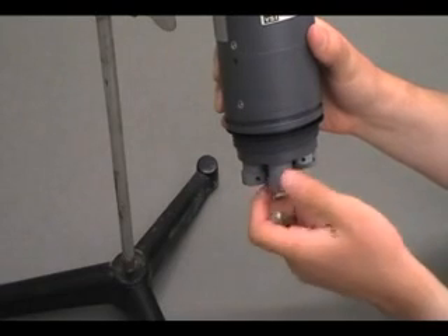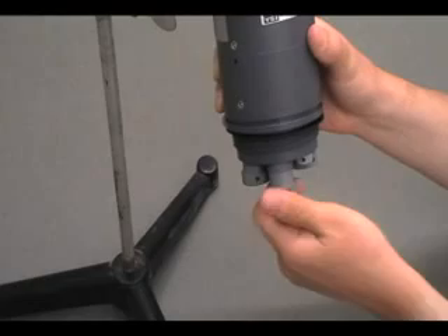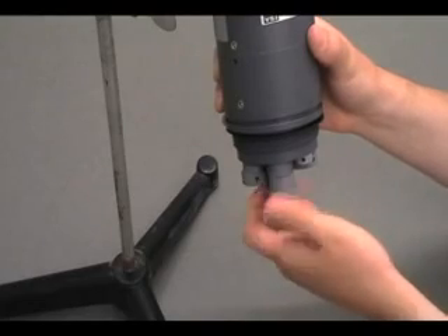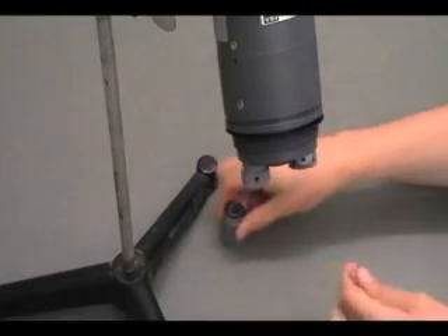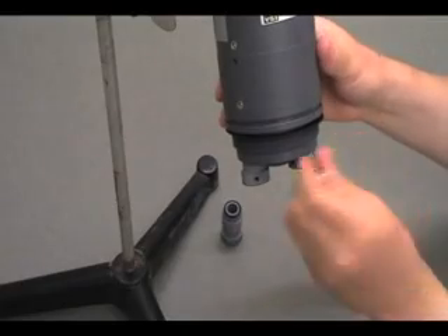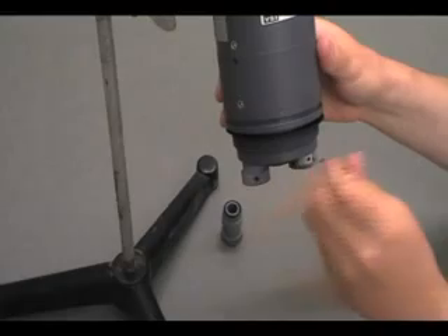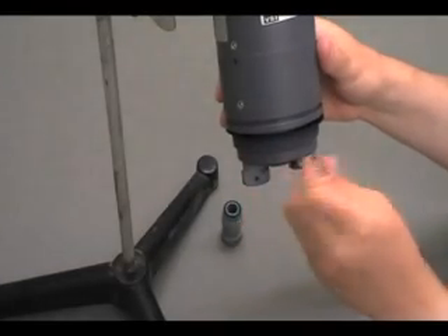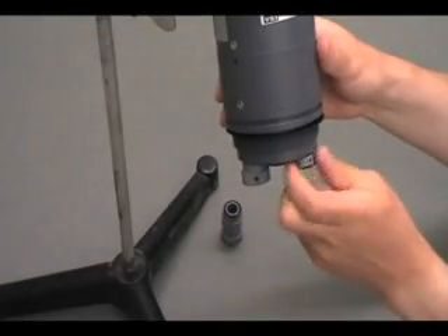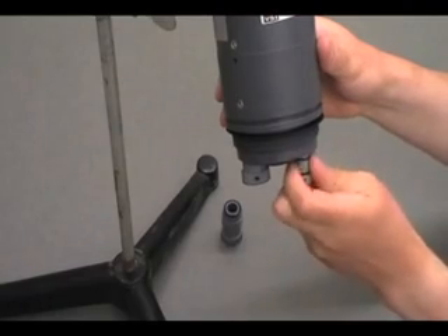Always remove plugs and sensors from the sonde with that end of the sonde pointed towards the ground or floor. If there is water present on the sensors or plugs, removing them as they are pointed down will allow water to drain away and prevent any flow of water up into the electrical connections inside the ports.